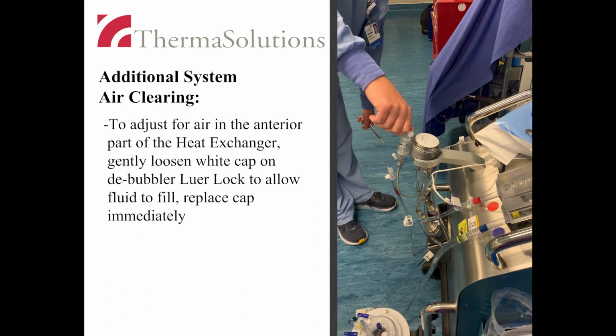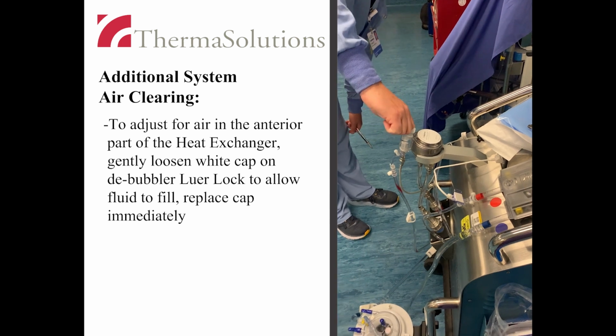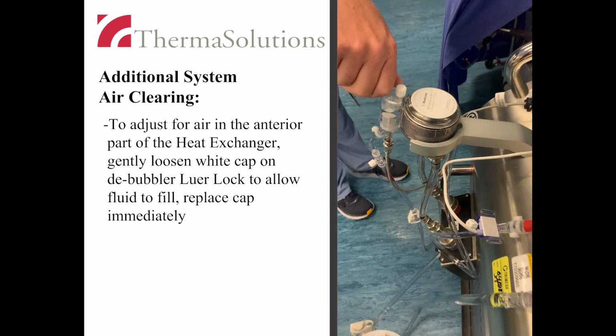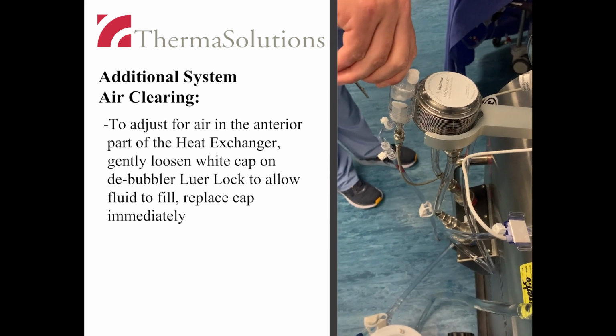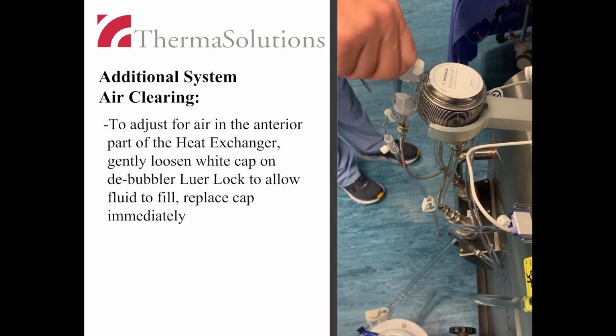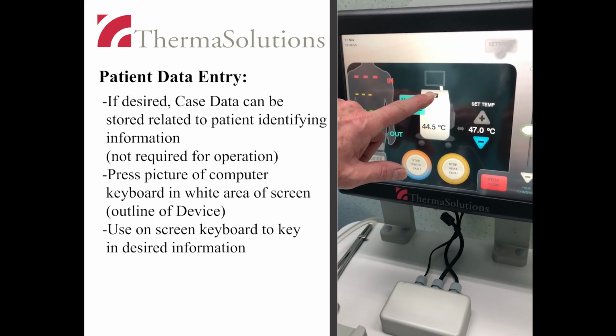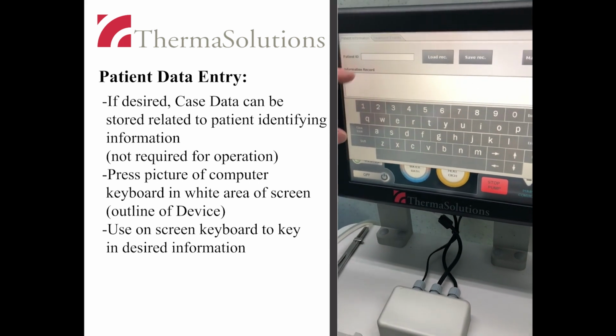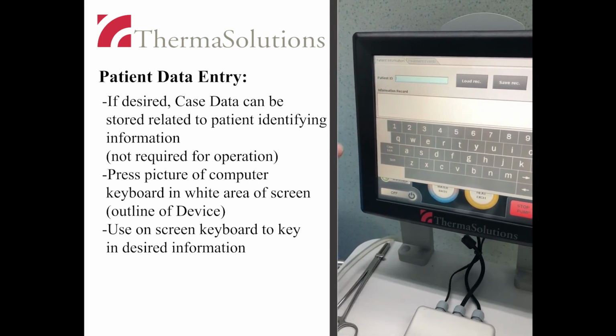If air remains in the patient fluid side of the heat exchanger, the air can be evacuated via the debubbler luer lock on the top of the heat exchanger. Loosen the luer cap to evacuate the air, then firmly retighten the cap. Patient data entry is possible if desired in order to link the case data to the patient. Touch the picture of the computer keyboard in the white area of the home screen. Use the on-screen keyboard to key in desired information for the case.